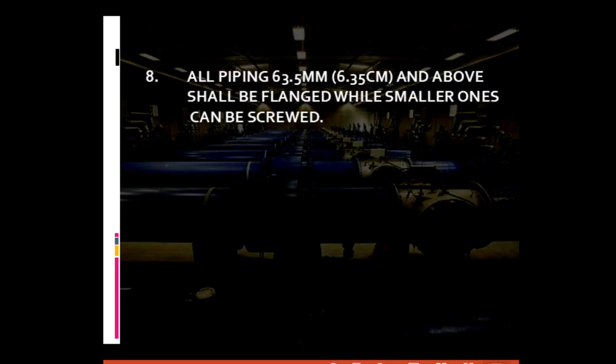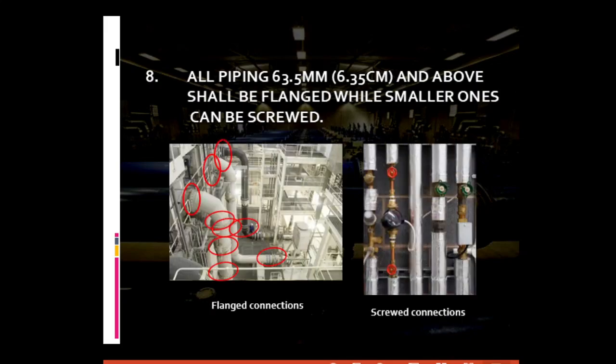For general piping requirement number eight: all piping 63.5 millimeters (equivalent to 6.35 centimeters) and above shall be flanged, while smaller ones can be screwed. Large pipe size diameters of 63.5 mm and above should use flange connections — a connection characterized by a pair of circular plates bolted together. The reason threaded connections are not used for large sizes is that there is no available pipe wrench or device that would turn large pipe sizes if they were threaded instead of being bolted by flanges.